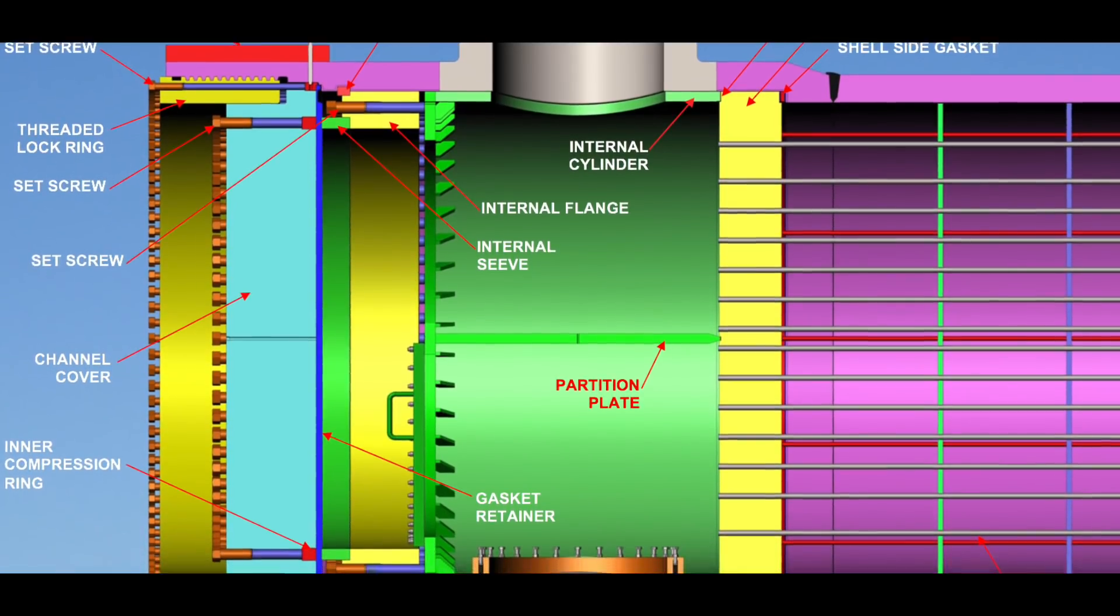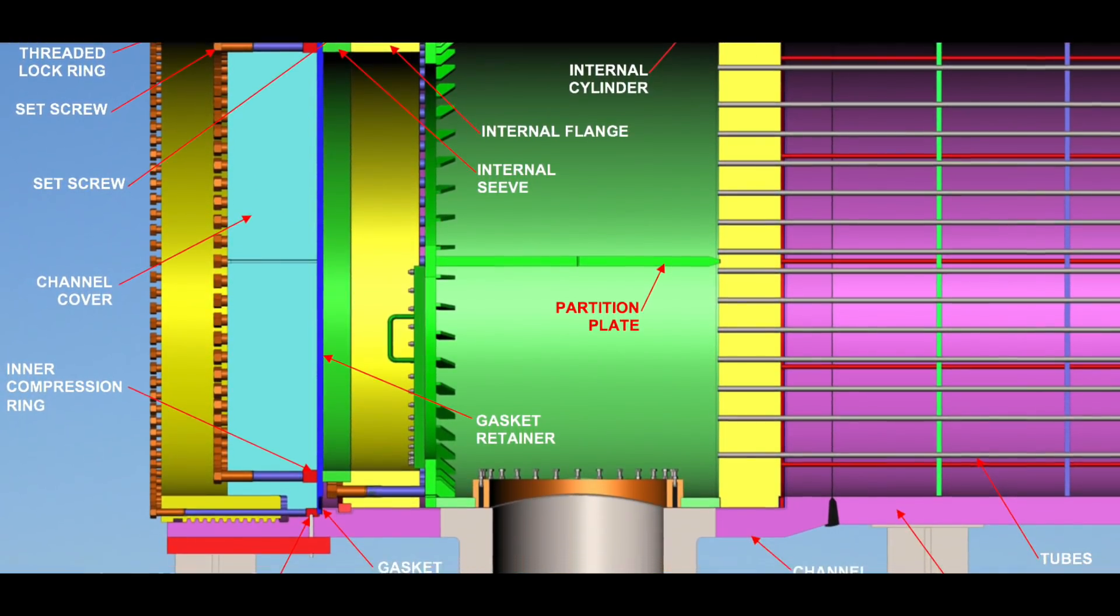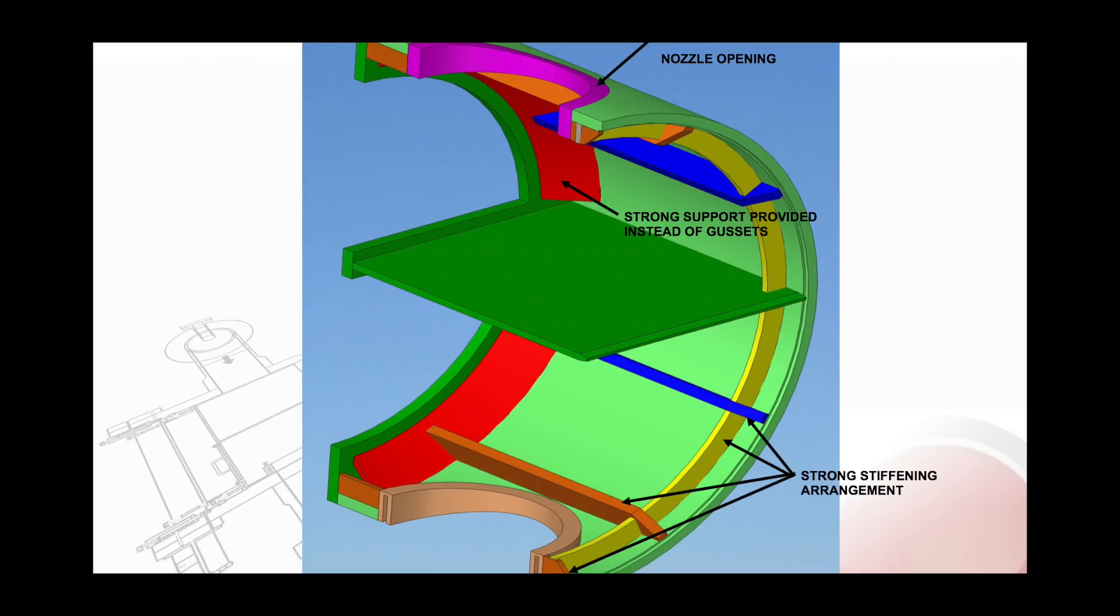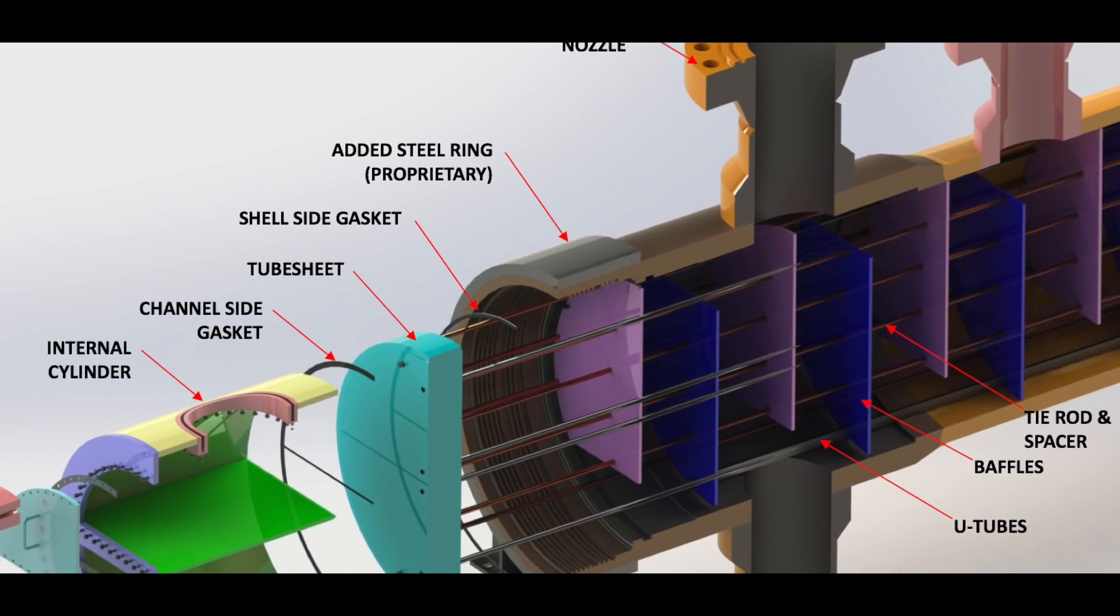Point 8: Where the shell side pressures are higher than the tube side pressures, the channel cylinder has to be rigid enough to uniformly transfer the bolt load to the gasket.